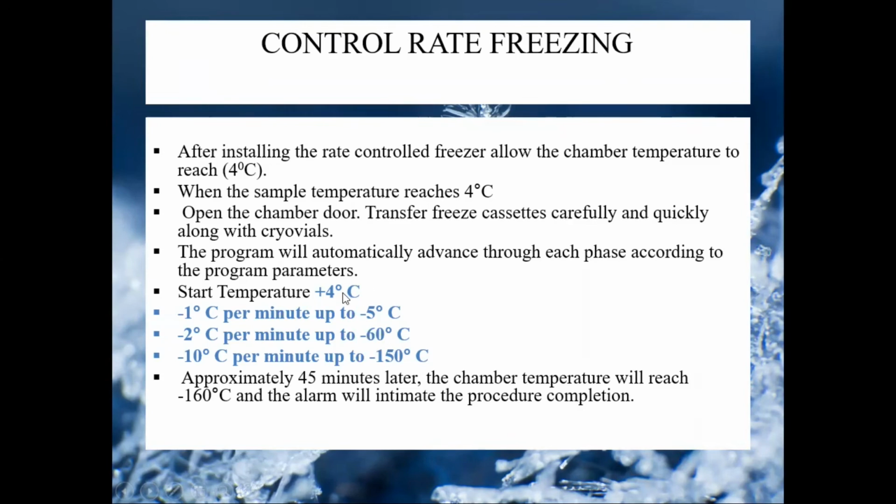All these processes will take approximately 45 minutes. After 45 minutes, the stem cell temperature from 4 degrees Celsius will reach -150. After -150, around -160 degrees Celsius, the machine gives an alarm. That means the completion of controlled rate freezing.